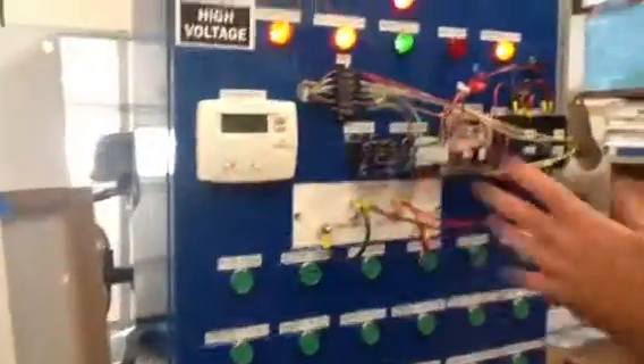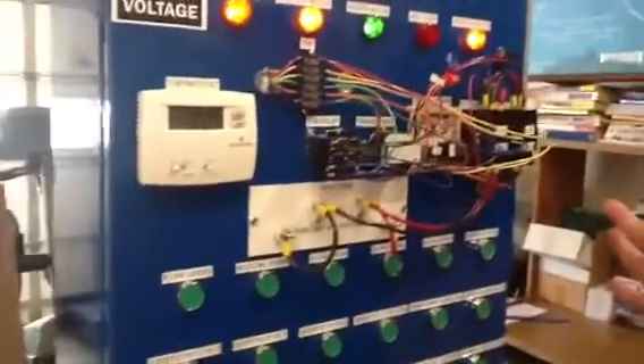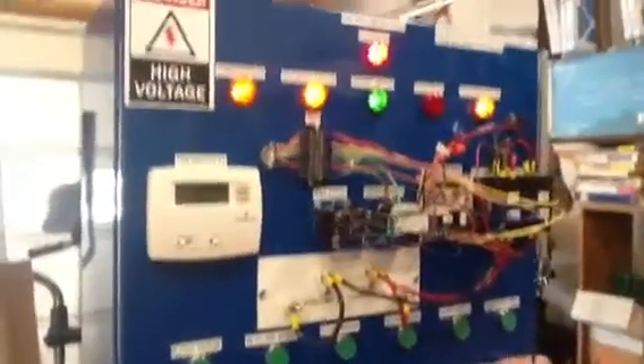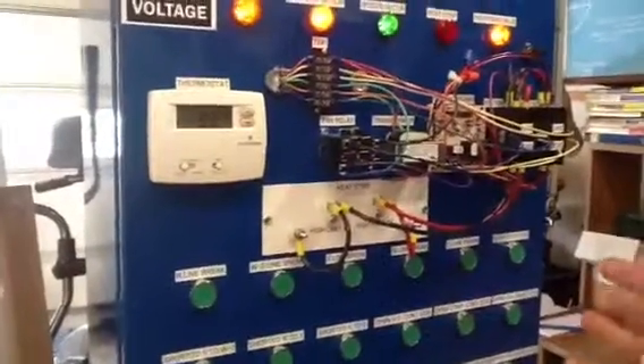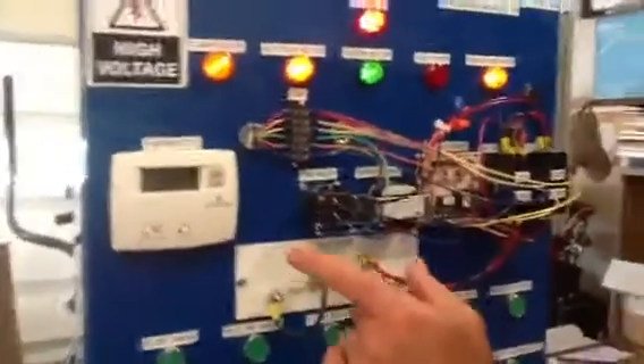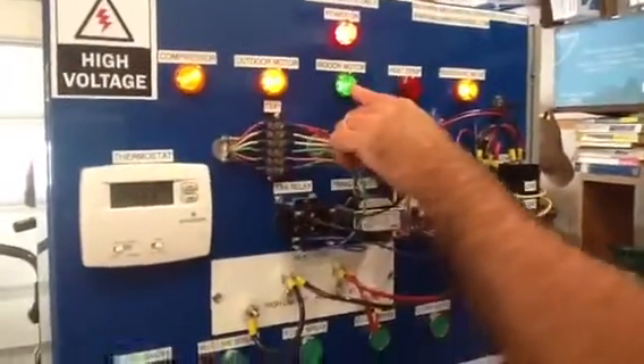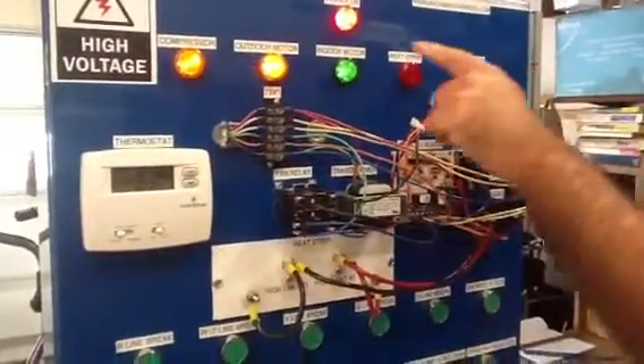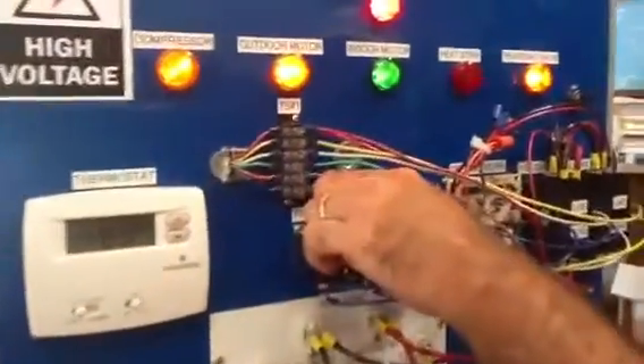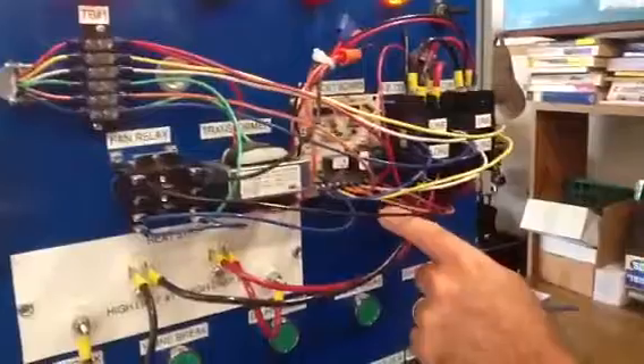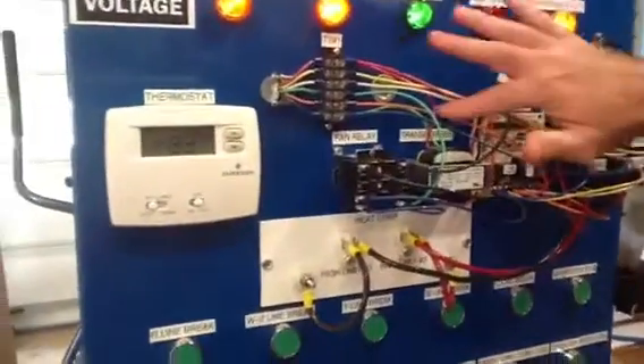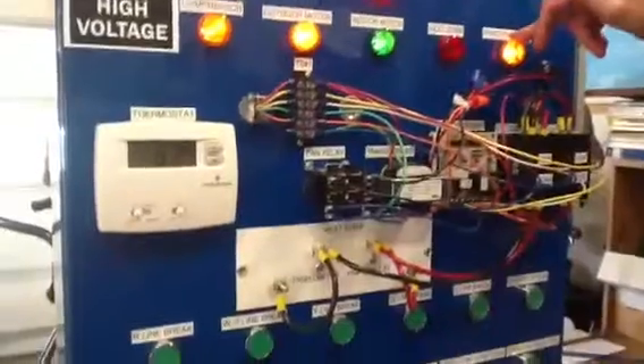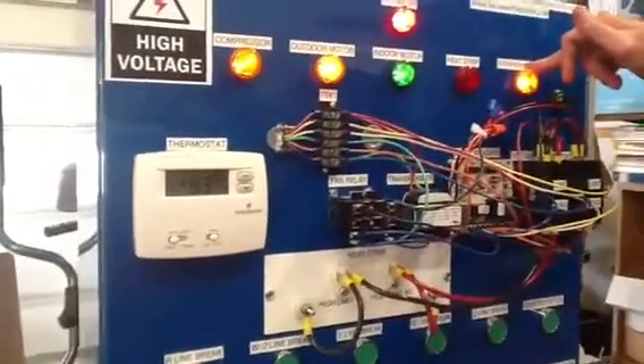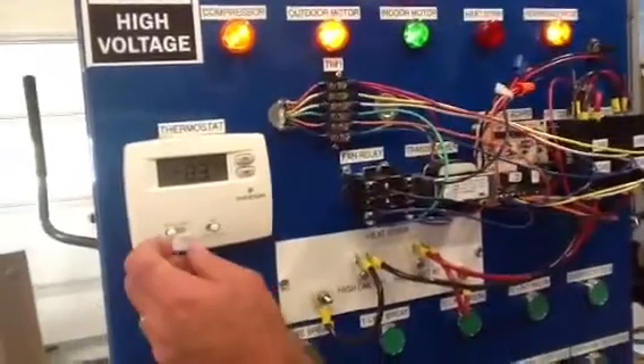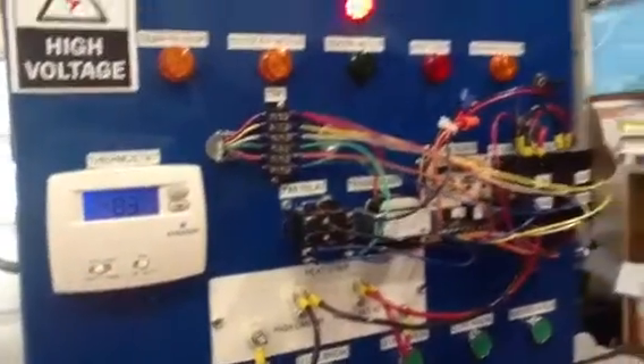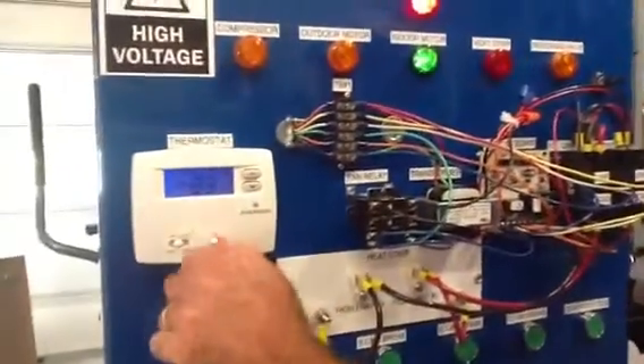Now, you would actually go through the entire function of the trainer. Basically, that means manipulate the thermostat into all functions to make sure that everything is working. So, we are in a cooling call: compressor, outdoor motor, indoor motor, and reversing valve are energized. If you look closely right here, this is an orange wire, and it is O on the terminal board of the defrost board. That means that the reversing valve is energized in cooling and de-energized in heat. It also energizes in a defrost mode. So now we're going to go to off position. Everything shuts off. Fan on by itself.